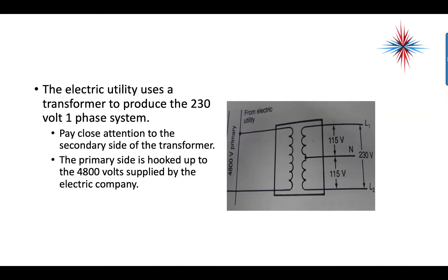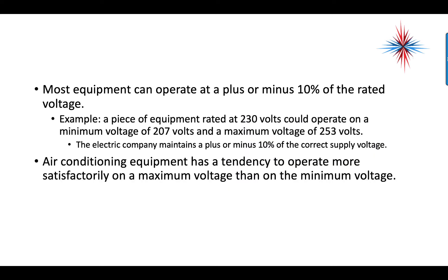The electric utility uses a transformer to produce the 230-volt single-phase system. Pay close attention to the secondary side of that transformer. The primary side is hooked up to the 4,800-volt supply from the electric company. On the pole, there's a transformer with a center tap — that is the neutral — and L1 and L2 come out on each side as the power wires. Most equipment can operate at plus or minus 10% of the rated voltage. For example, equipment rated at 230 volts can operate on a minimum of 207 volts and a maximum of 253 volts.